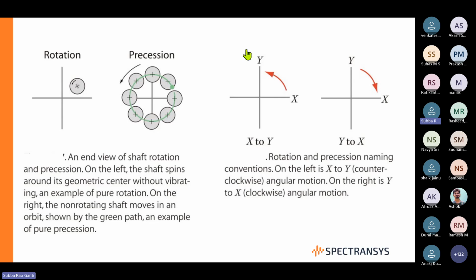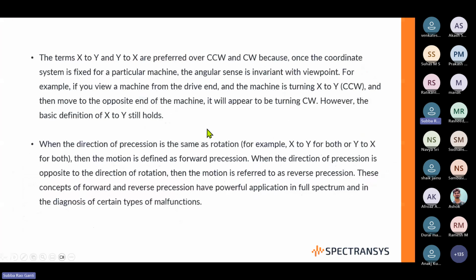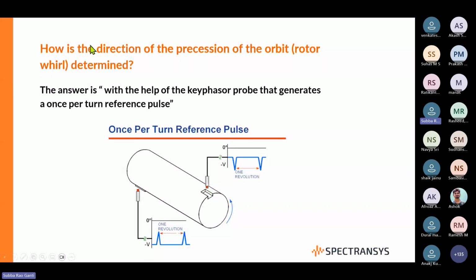Now, how do you identify the precession? How do you give the direction? Normally, for precession, we don't use the words clockwise or anti-clockwise. We try to identify the precession with respect to the probes - X to Y probe, the precession is in the direction from X to Y probe or from Y to X probe. If the direction of rotation is also in the same direction, we call it forward precession, otherwise reverse precession. So precession is normally mentioned with respect to the probe, X probe to Y probe being the direction of precession.